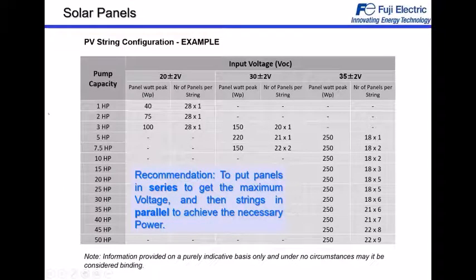Here is an example of PV string configurations. Depending on the pump capacity, we need to put some panels in series, and sometimes we need to put strings in parallel to achieve the power of the system. And of course, it depends on the characteristics of the panel, whether it's 20 or 30 or 35 volts, and also the power, which is the watt peak that the panel is giving. Normally, the engineering company or the company offering the panels can give all this information. The recommendation is to put the panels in series to get the maximum voltage, and then strings in parallel to achieve the maximum necessary power.